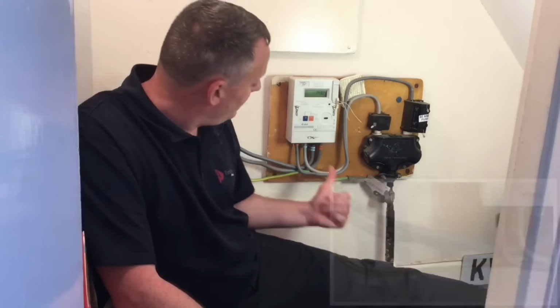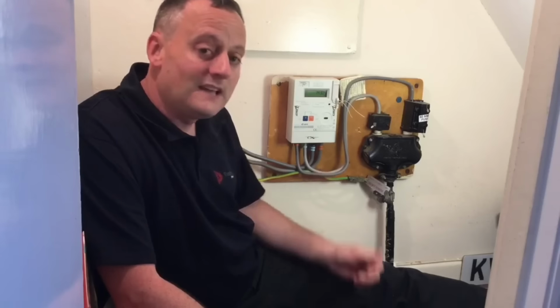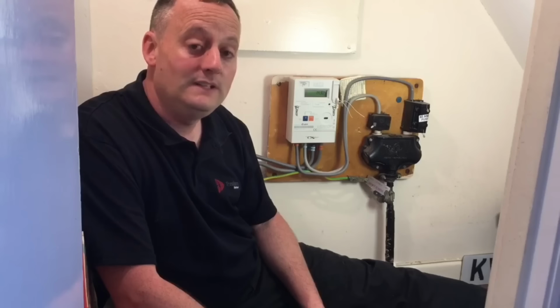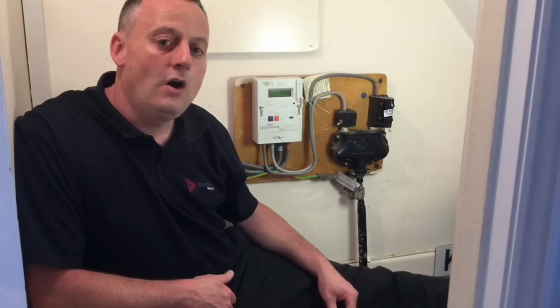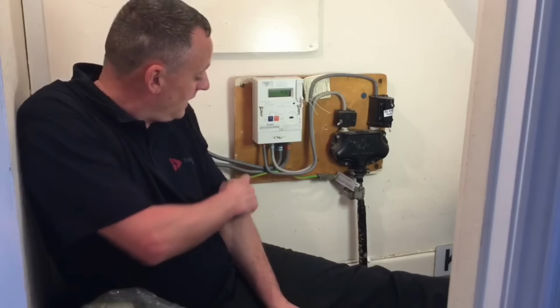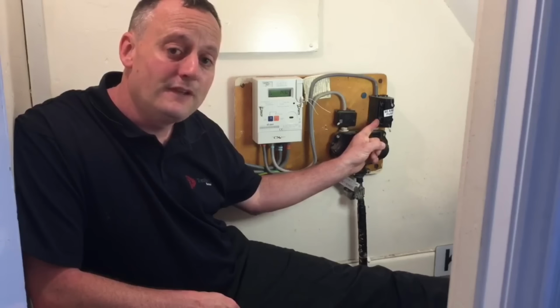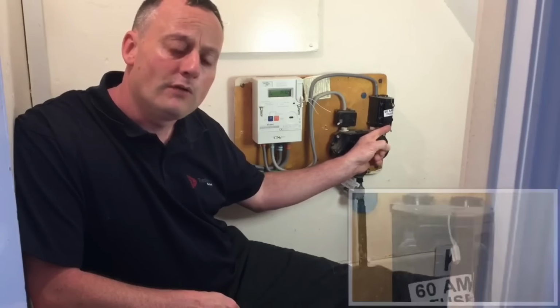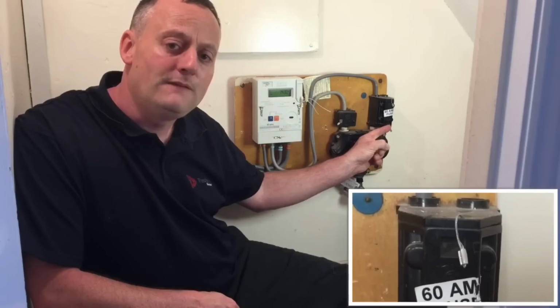Please note in this installation, on the supply authority's side of the meter, the tails are 16 millimeters squared and not 25 millimeters squared. This installation, unlike the previous one we looked at for the TNCS earthing arrangement, has no double pole switch inserted in the tails. So in these tails here, we cannot isolate the consumer's unit itself. Isolation for the distribution board has to occur within the distribution board itself. So in the event of you requiring to change the distribution board, you would need to pull out, in this case, the 60 amp fuse, which is sealed by the supply authorities, and you would require permission before breaking those seals.